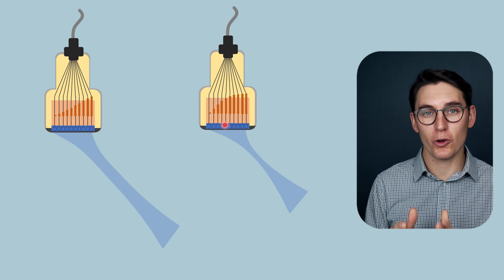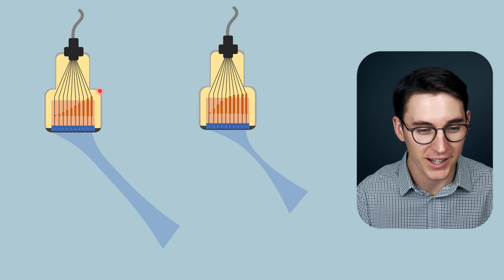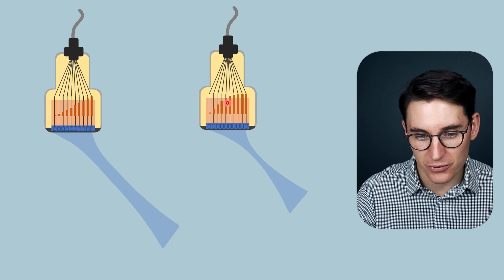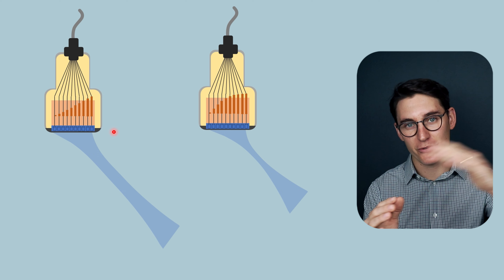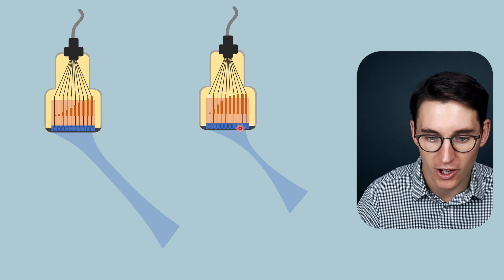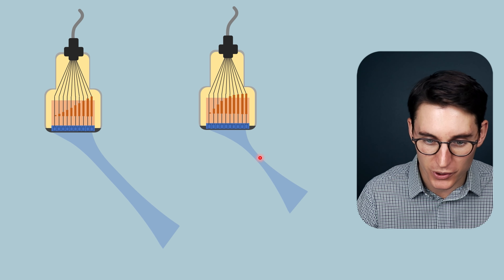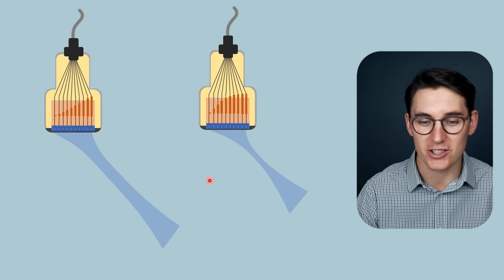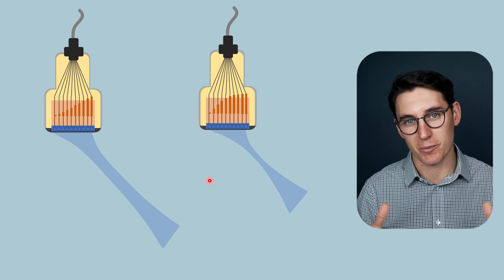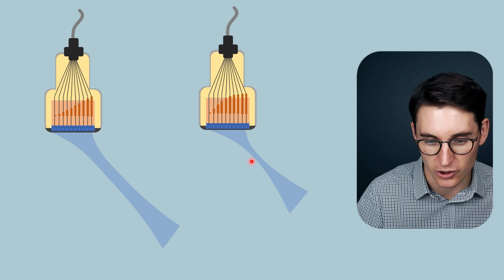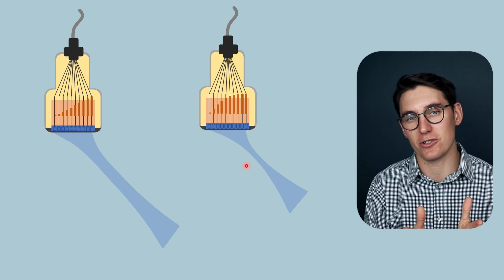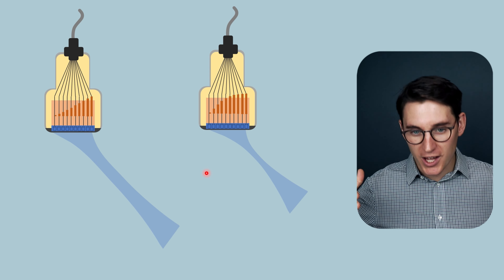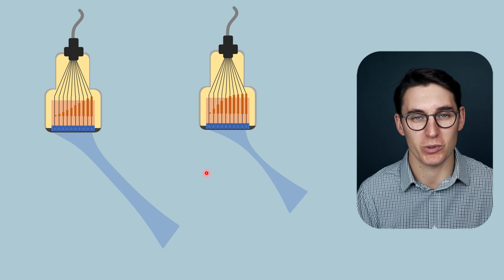Beam steering and beam focusing can also be combined. With the beam steered to one side, adding a further delay in the timing of the transducer elements brings the focal zone closer to the transducer. This not only brings the focal zone closer but also narrows its width, improving lateral resolution. So focusing a beam also provides a resolution benefit — the more we focus it, the better the resolution we achieve.